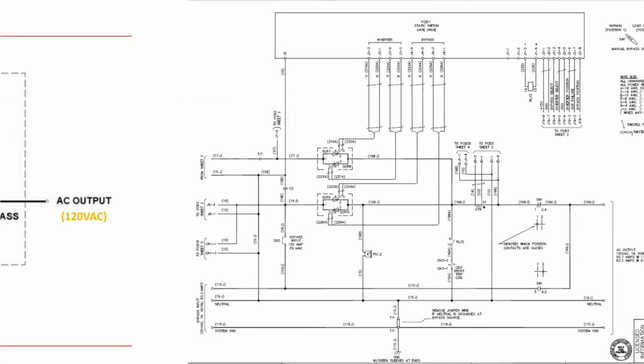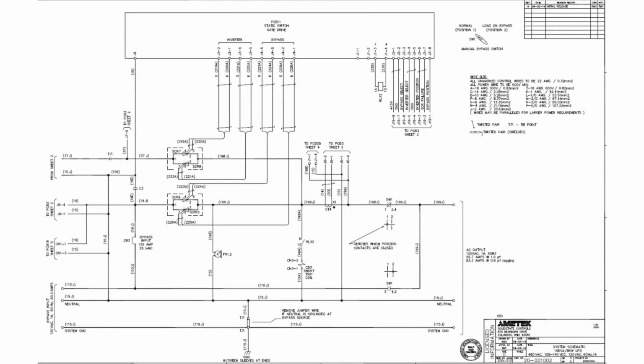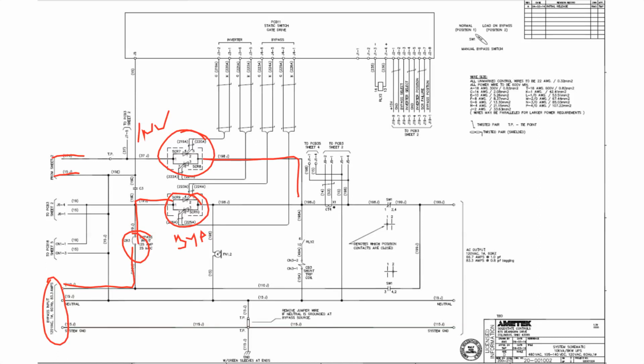Okay. In the schematic drawing, it's drawn a little bit differently, but it's still the same. On this one here, this is the inverter static switch. I just know that because I know wire 17 and 15 come from our inverter. But I do know that it says down here, our bypass input is down here. So if we follow this up, it goes up through this bypass input breaker, up through here, in here. So I know for sure that this is our bypass static switch. And then you can see that the output of both static switches is connected together. And that is our common bus. That is our critical bus, basically. We can swap between inverter supply or bypass supply, and we will maintain the circuits out to our critical loads that are connected to the AC output here. Okay.